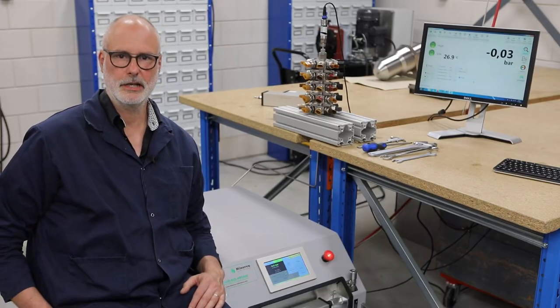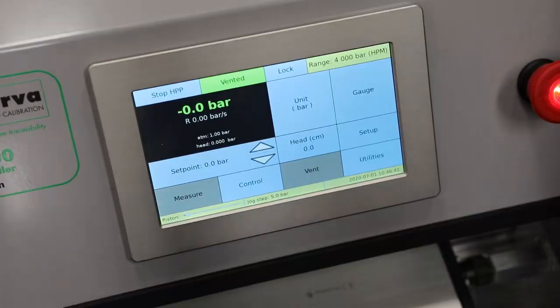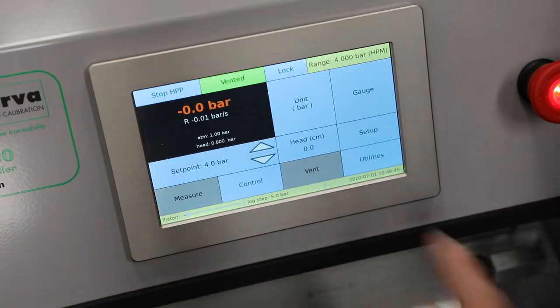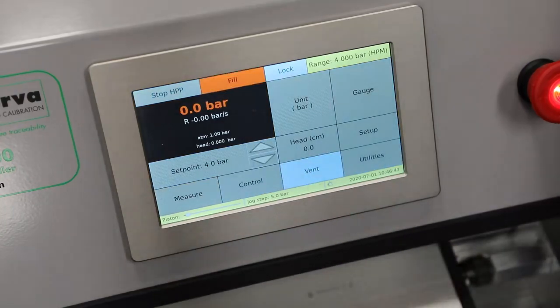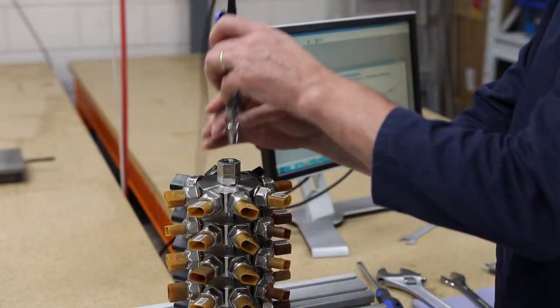Before starting a calibration, typically there are a couple of things to do to assure a smooth calibration. First of all we have to fill the attached tubing and manifold and make sure we have done our best process to remove air from the system. The HPP has a fill routine and a unique vacuum purge function to remove air from the attached manifold.